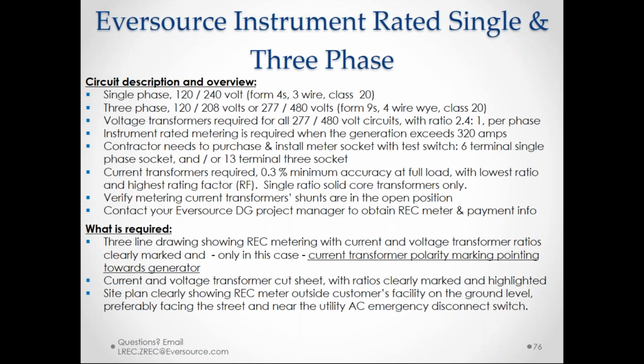Obviously, meter engineering will review that, and if we concur that the ratios are correct or sufficient, we will approve it. However, if we find that the ratios are not in keeping with what they should be, we will determine and recommend that they be adjusted and the drawings be revised. As well, if we feel that the proposed CTs or VTs don't meet the requirements for accuracy and range as dictated by the program, we will also select a different model.